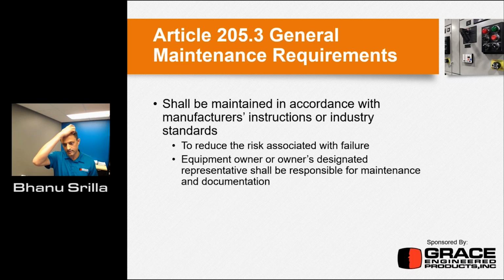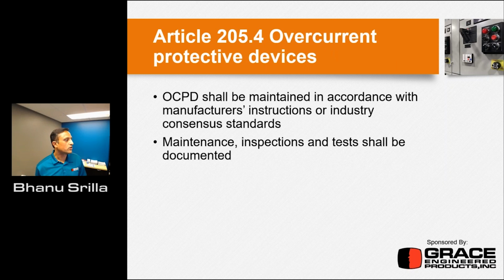When I say shall, it is like mandatory language. It is like a legal language you must adhere to. Okay. So Article 205.4, overcurrent protective devices. OCPD shall be maintained in accordance with the manufacturer instructions or industry standards, and maintenance and inspection tests shall be documented as well. Not only do you perform these things on a regular basis, but the maintenance guidelines are required, and you also need to make sure that these things are documented and test reports are kept in place as well. Because if you don't have the documents in place, then it means that it did not happen.